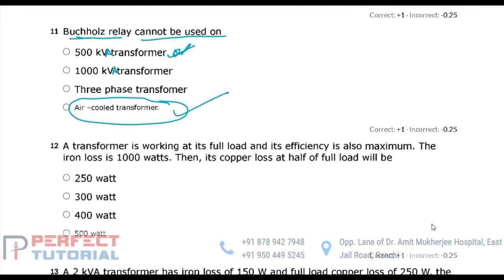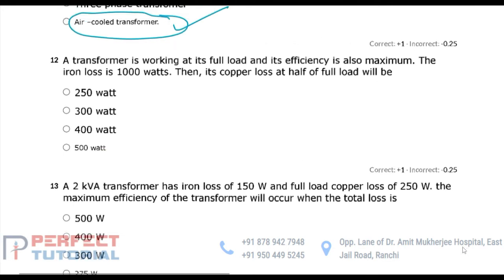Okay. Next सवाल है a transformer is working at its full load and its efficiency is also maximum. The iron loss is 1000 watt, then its copper loss at half of full load will be. Efficiency ट्रांसफार्मर का मैक्सिमम अकर हुआ है और ट्रांसफार्मर ऑपरेट भी हो रहा है फुल लोड कंडीशन में. अब आप जानते हैं at maximum efficiency, the loading at which maximum efficiency occurs, copper loss equals iron loss. So indirectly दिया हुआ है full load copper loss is equal to iron loss that is equal to 1000 watt. Means full load copper loss PCU is given as 1000 watt.